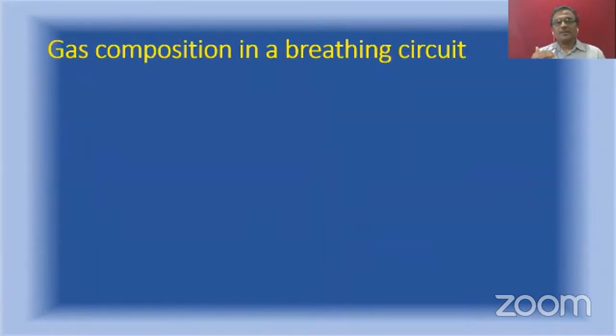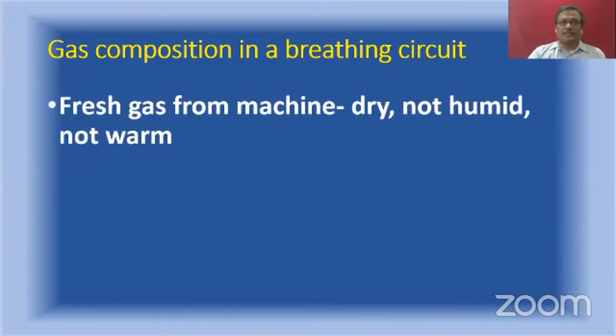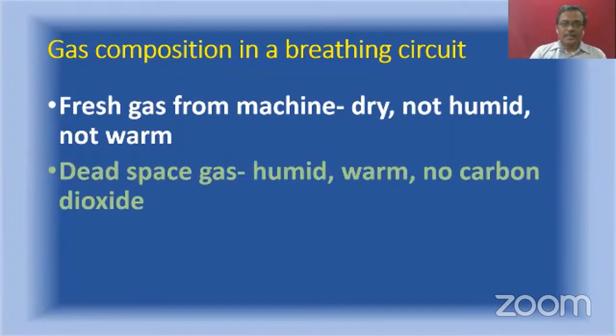Now, what about the gas composition in a breathing circuit? This is also very much important. Actually, this gas composition determines how much rebreathing happens, how much gas is wasted and going out to the atmosphere. One is the fresh gas, which is coming from the machine. It is dry, there is no humidity, there is no warmth. And the second gas is the dead space gas.